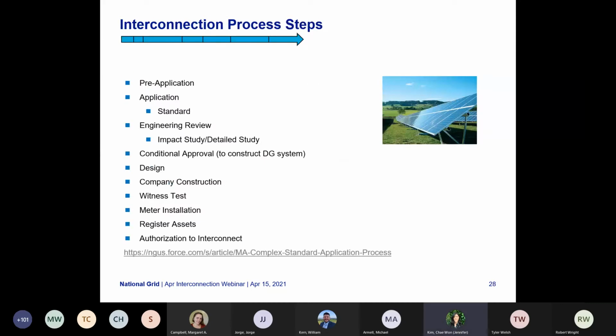The interconnection process steps are: first you submit a pre-application, then the application, which once in the screening process will determine it needs to go down the standard process. At that point we have the engineering review, which is an impact study, and a detailed study could be required if it's a complex enough system. Then we have the conditional approval, the ISA, to have the agreement to construct the DG system. Once that's done, payment is received and design starts, followed by company construction. Once everything is done, we can have the witness test, install the meter, register the assets, and give ATI.